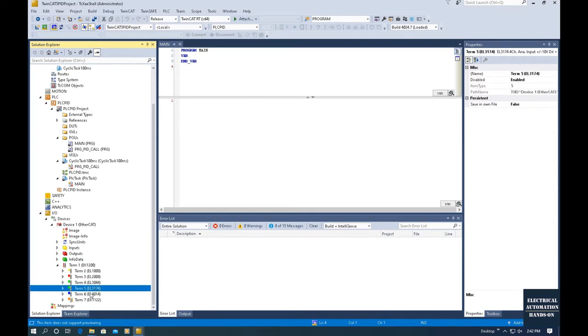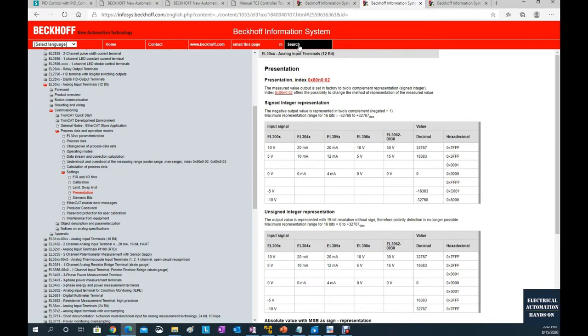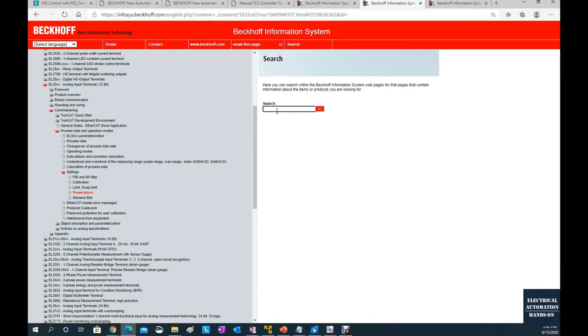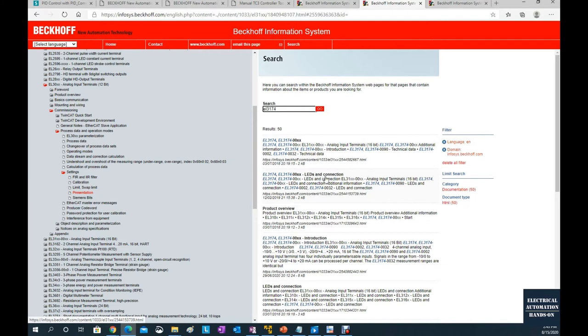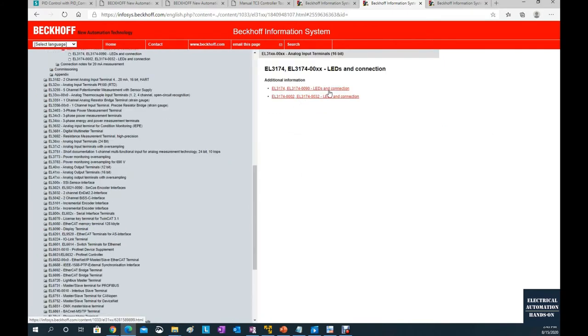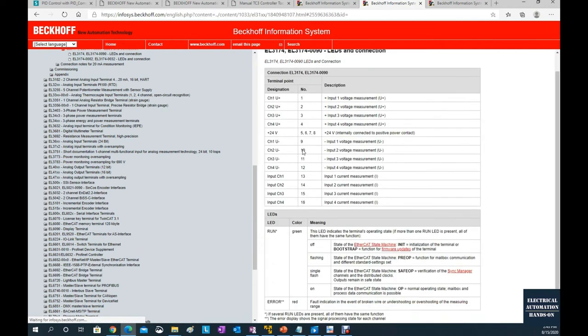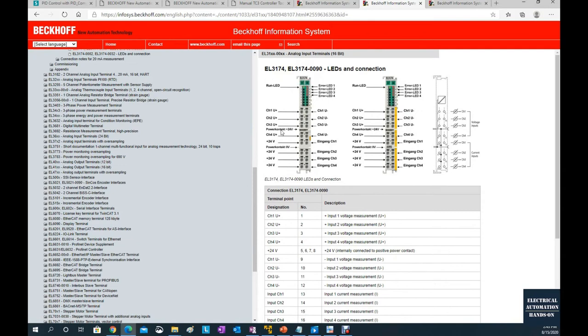Now let's look at the EL3174 in detail — this is also a commonly used analog card, but using it is a little more complex. Let's search for EL3174 in the documentation. First, go to the connection section to check the wiring. The EL3174 has four analog channels, and each channel can be used as either current or voltage — but current and voltage cannot be used at the same time. I'd like to mention how to wire the current and voltage channels.